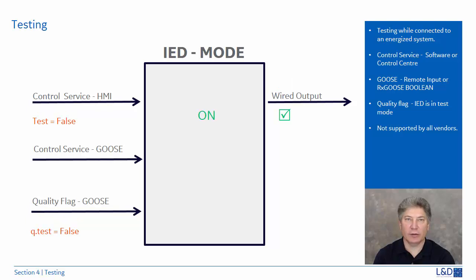Next, we'll take a look at the mode set to on. Here, once again, the test is equal to false, the Q.test is set to false, but the outputs are active. Next, we have the mode where it's set to test. So of course, the test bit is equal to true, the Q.test is set to true, and we have the ability to force the contact outputs for testing.